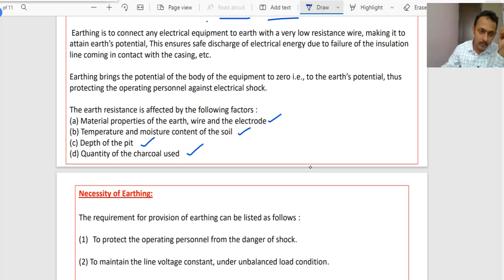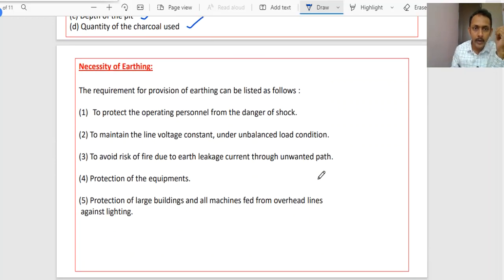Now with respect to the necessity of earthing, it is going to protect the operating person from the danger of shock, and earthing is required to maintain the line voltage constant under unbalanced load condition. For example, if any three-phase load is connected to the system, whether in star or delta manner, and an unbalanced condition occurs, it results in some amount of current flowing through the neutral wire, right? As long as the system is perfectly balanced, the current flowing through the neutral wire will be 0, right? So to maintain the load line voltage constant under unbalanced load condition, this earthing will be useful, and also to avoid the risk of fire due to earth leakage currents through unwanted paths.